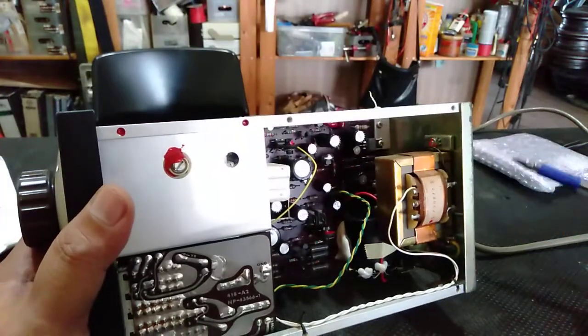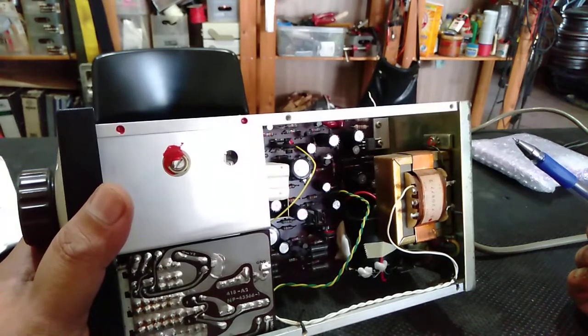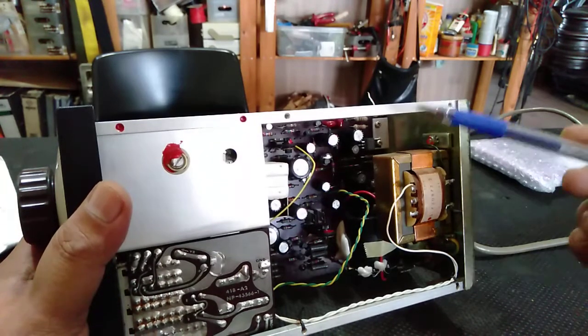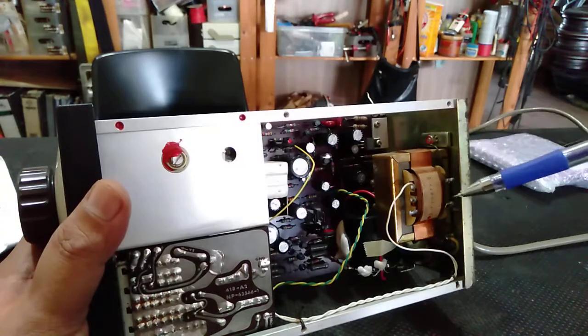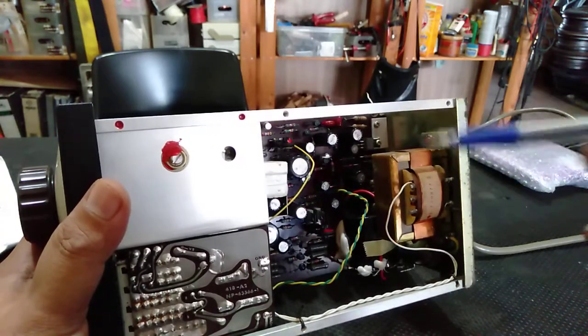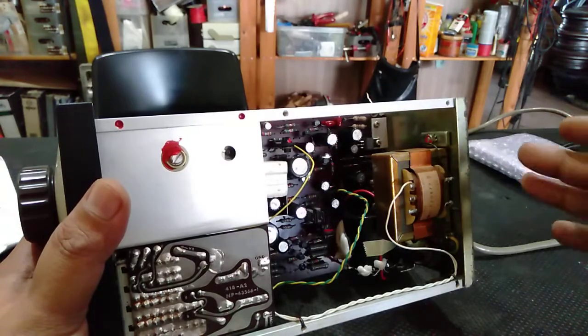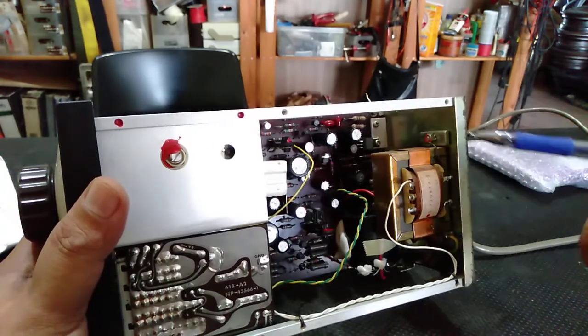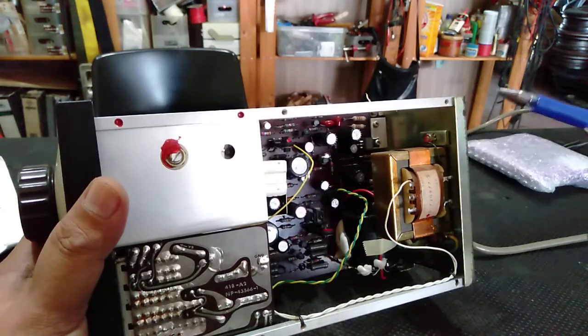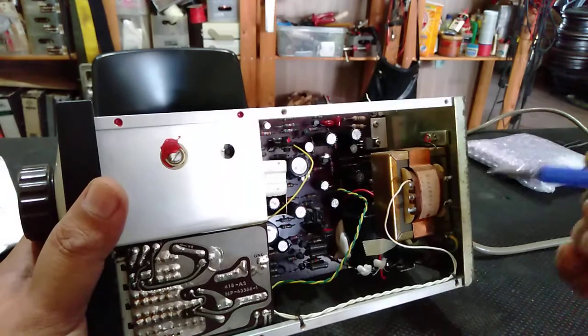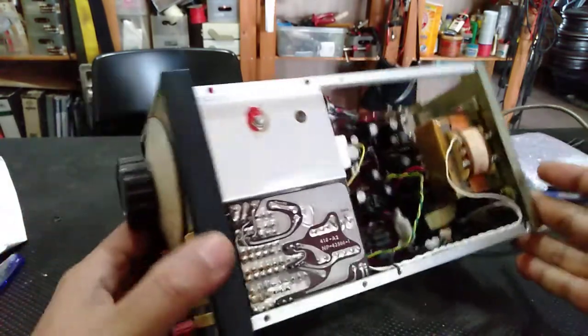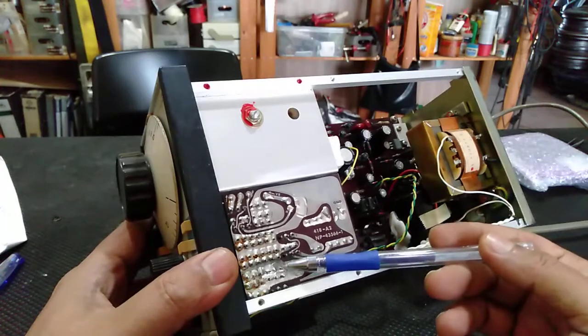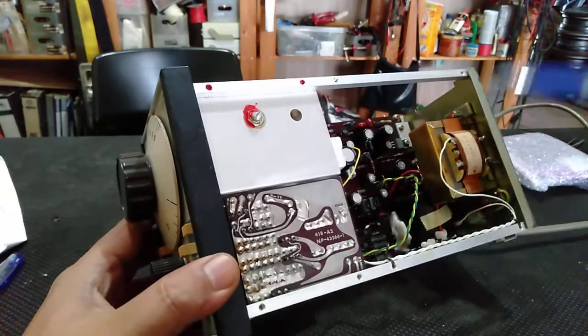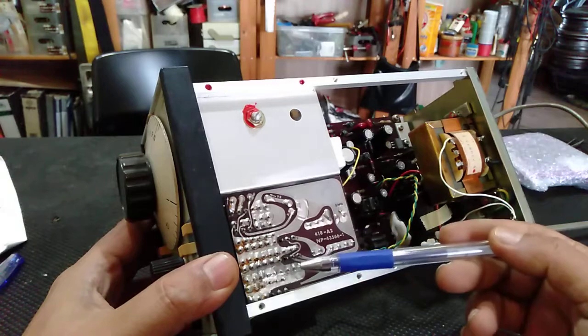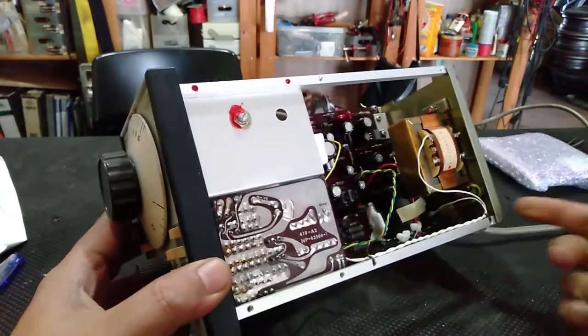The service manual is not available, but in the operation manual there is an adjustment procedure, and there are some points to check, for the user to follow to do some calibration on it. And I did check the power supply. It seems okay, and then I decided to do some soldering here after the other board.